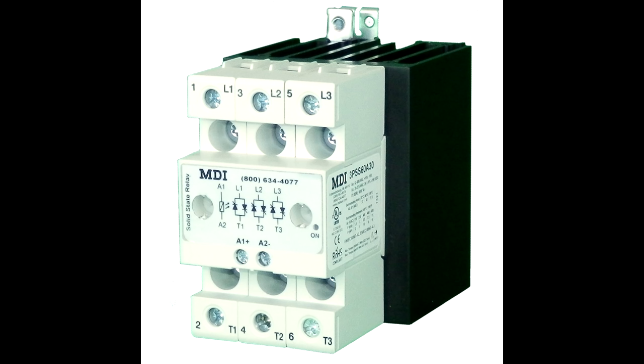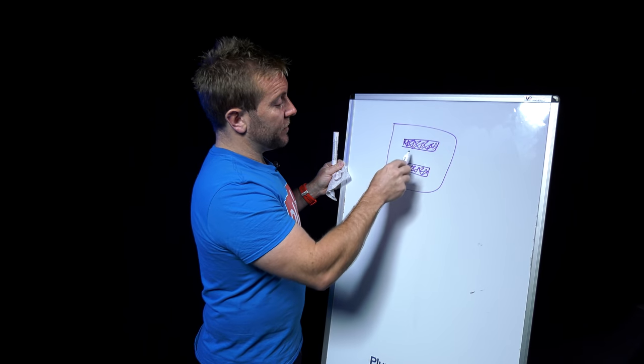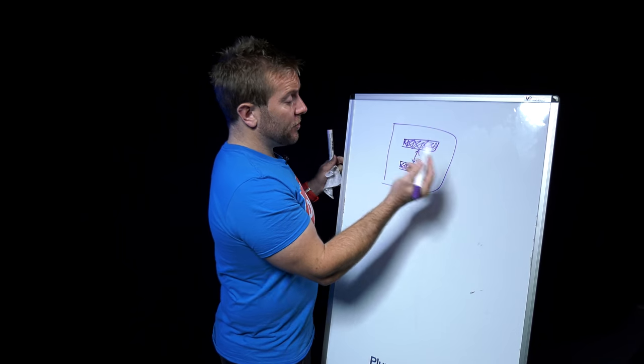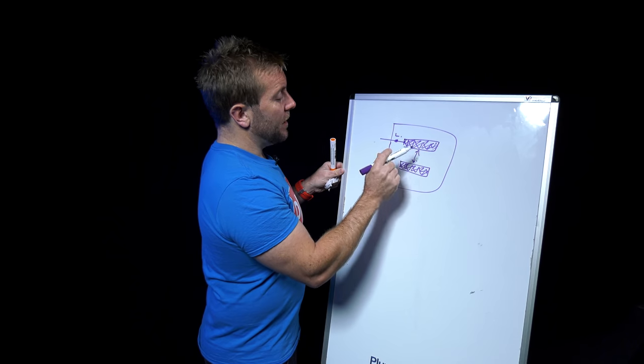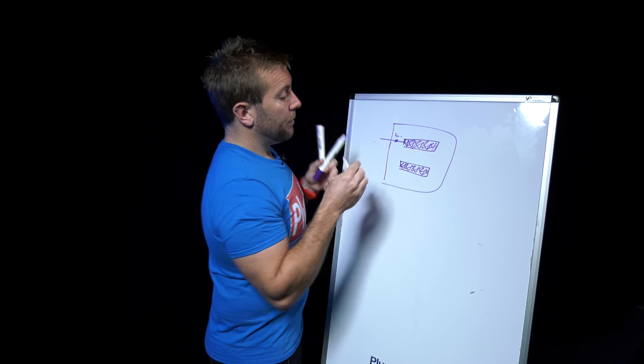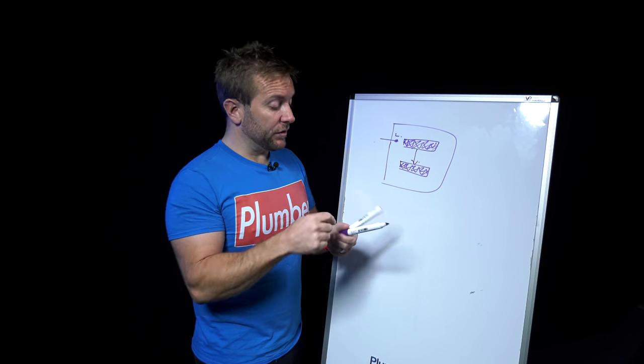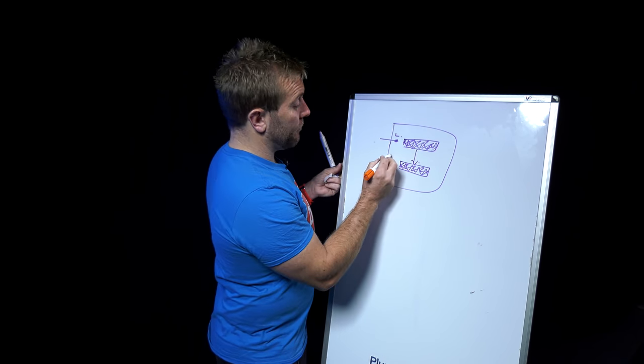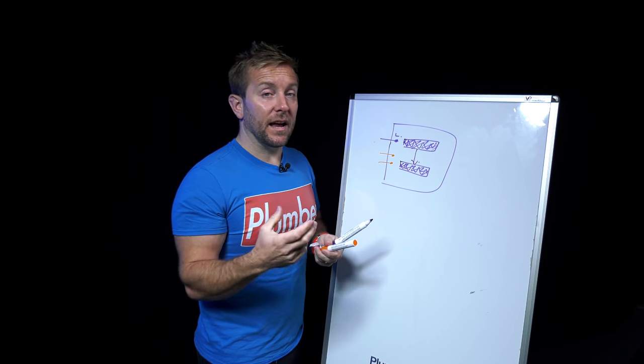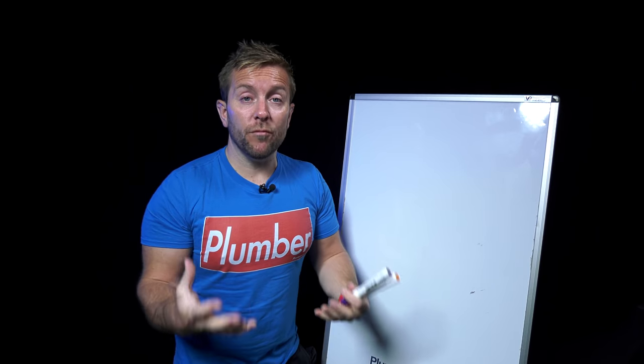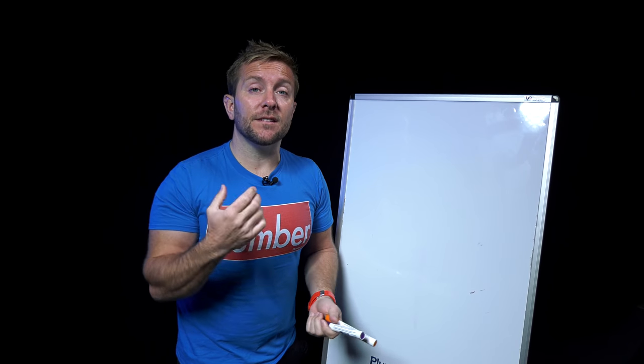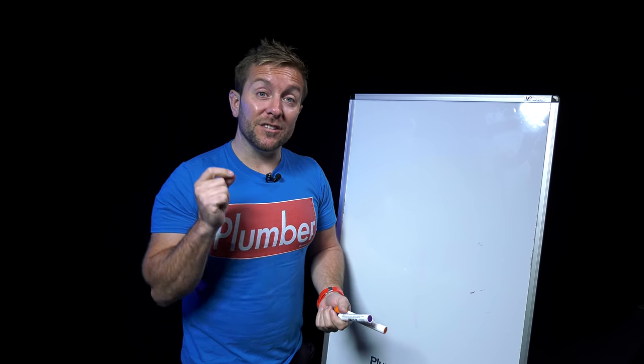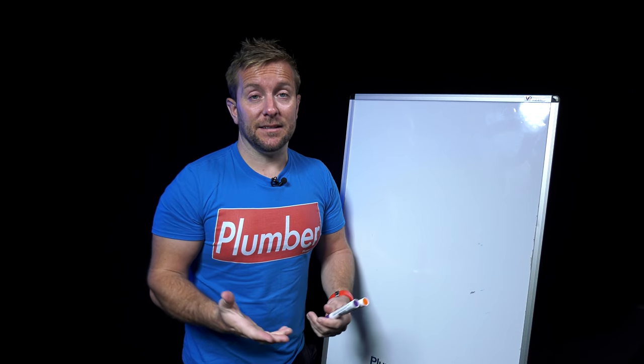So quickly, what is a relay? A relay is a set of two contacts that often, in the same way as what you get on a solenoid valve, move up and down and make contact when an electrical current is applied. So what's handy about that? So usually what you have on a relay, let's just do a really simple relay. You've got a live that comes in and when that live is initiated and switched on by something, maybe the time clock, that will come down and make a contact between maybe some contact wires that we want on the other side. The good thing about that is that means that we can isolate one part of the system away from the other part of the system.